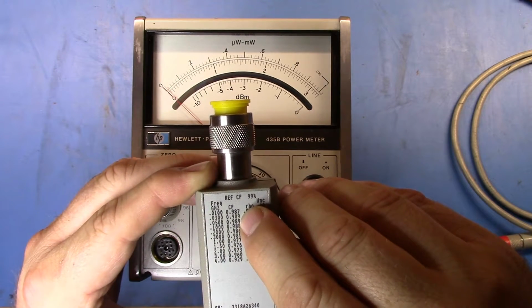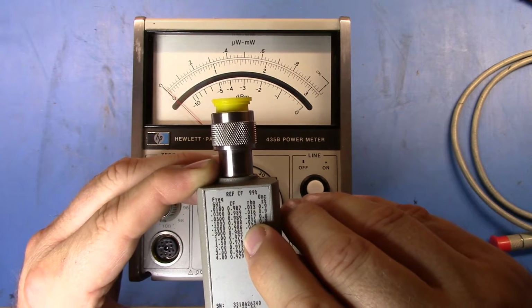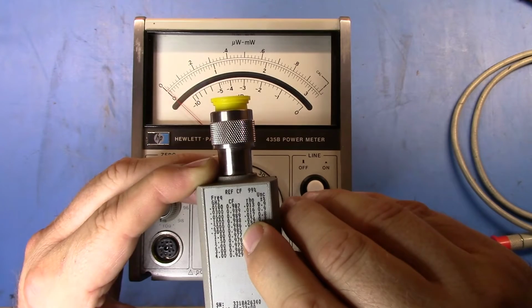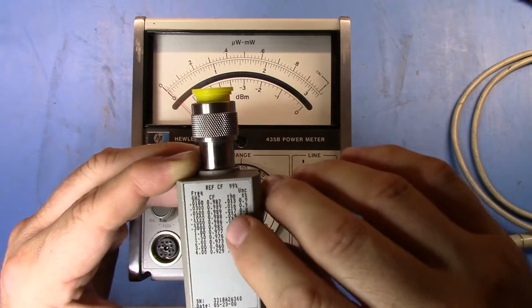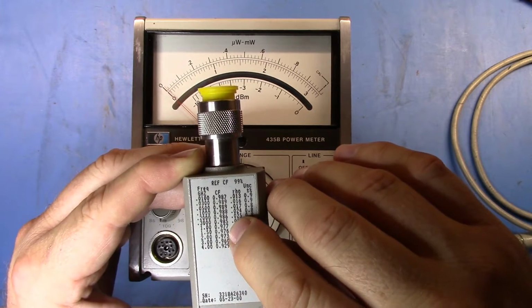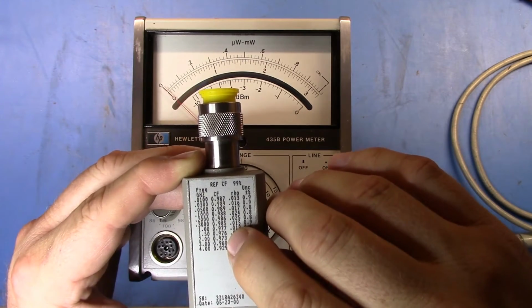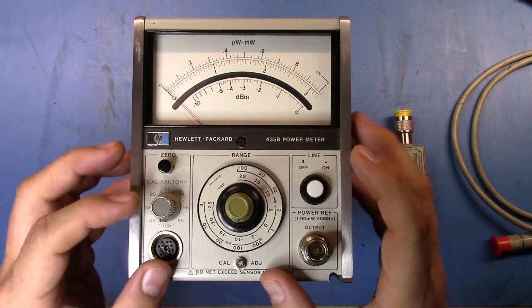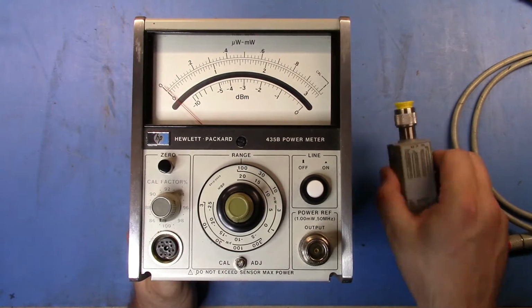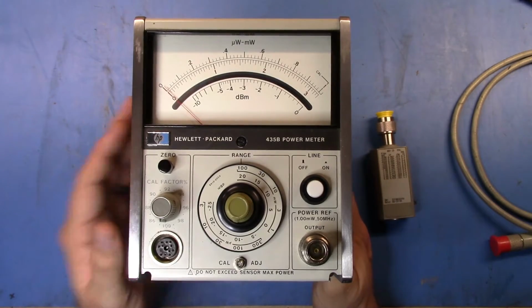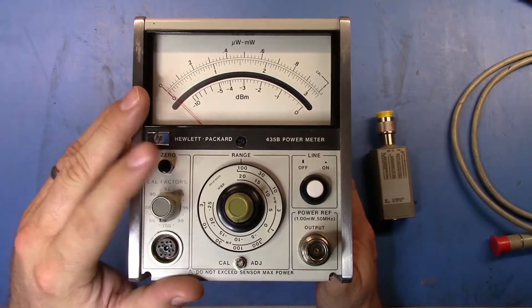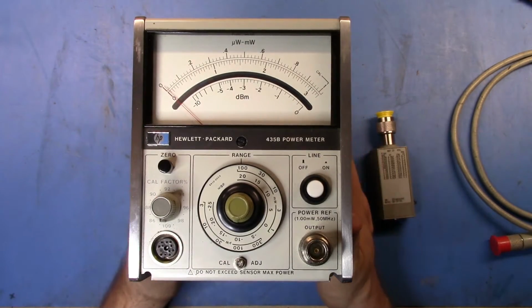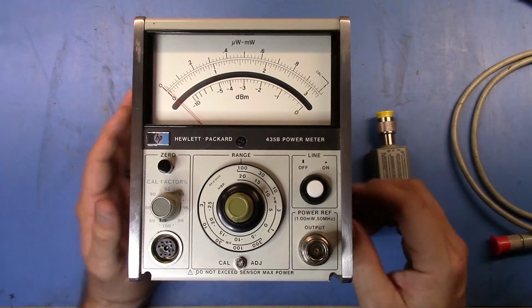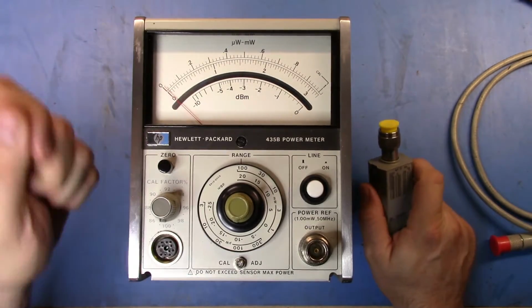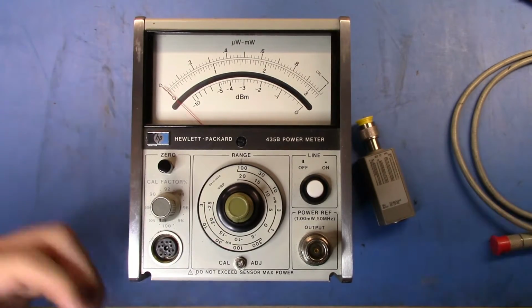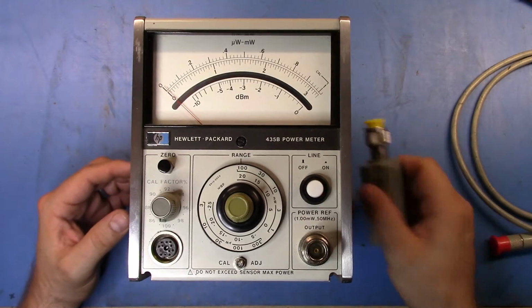and then it stays pretty much in the 98s all the way to 300 megahertz, and then it drops down to, so that'd be the 99 button that I'd have it on. And then it drops down to the 98 button basically until the end of 2 gigahertz, and then steps down again a little bit. So they're much more granular, whereas in the digital meters you have extra resolution to put that calibration factor in. So you'd set that calibration with the sensor, and then once you're there you'd press the 0 button, and this creates an auto feedback circuit that basically reads the current value of the bridges and then sends it back into the system and basically zeroes out everything so that you're ready to go and read.